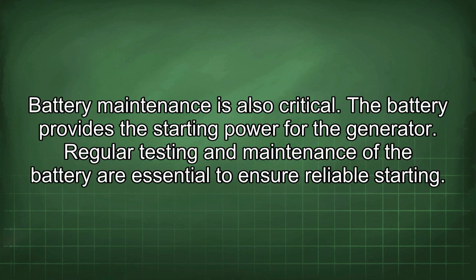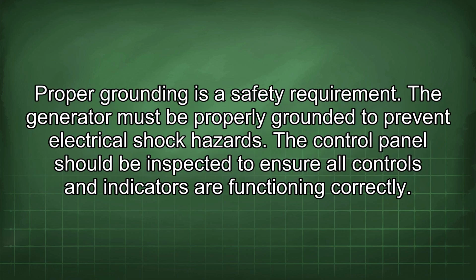Battery maintenance is also critical. The battery provides the starting power for the generator. Regular testing and maintenance of the battery are essential to ensure reliable starting. Proper grounding is a safety requirement. The generator must be properly grounded to prevent electrical shock hazards. The control panel should be inspected to ensure all controls and indicators are functioning correctly.